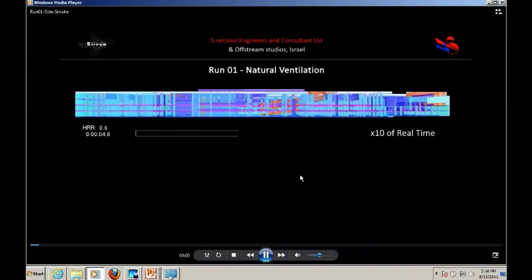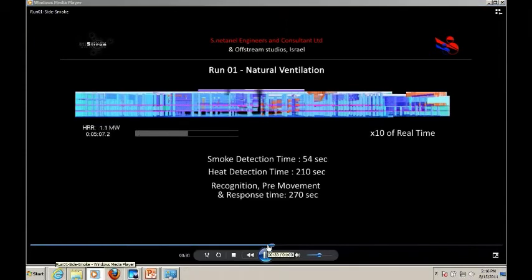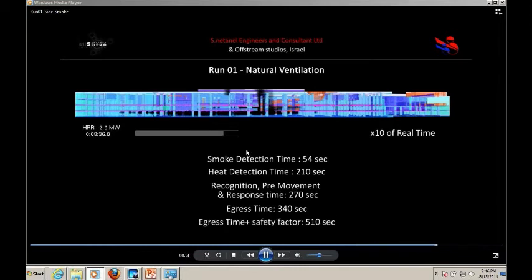I'm going to show you a side view so you can all see the way that this travels between the floors. You can see on the bottom is the level that has the burning car, and then level 3, level 2, and level 1, and smoke coming out through the main atria for natural ventilation and natural smoke control. All good, seeing that, traveling between floors.